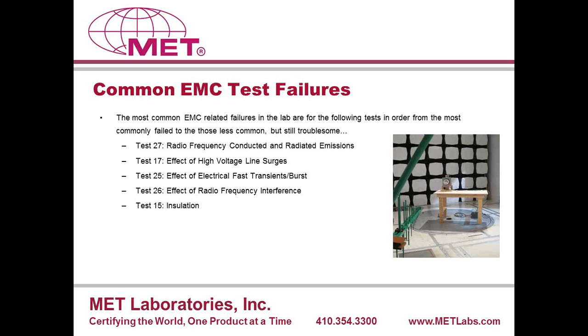And lastly, the insulation test, which is basically a dielectric test where you're testing for the insulation between the current carrying parts and other metallic parts of your product. And the requirement states that the leakage current limit is 5 milliamperes. And sometimes some of the products are not able to meet that requirement.